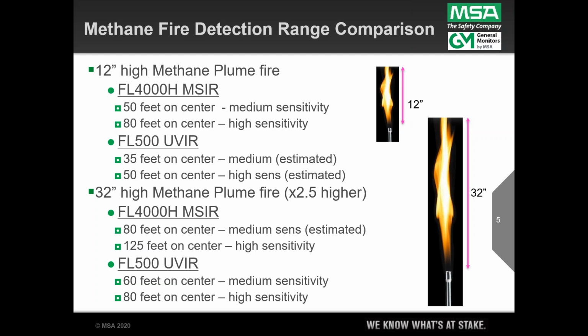That's the smaller fire, the 12-inch high methane plume fire, and that's used by Factory Mutual in their standard 3260 approval testing. When a manufacturer submits their devices to FM, they will test a 12-inch high methane plume fire. Now, an industry standard in some cases, an alternative standard, is a 32-inch tall or high methane plume fire. Again, this is 2.5 times higher.